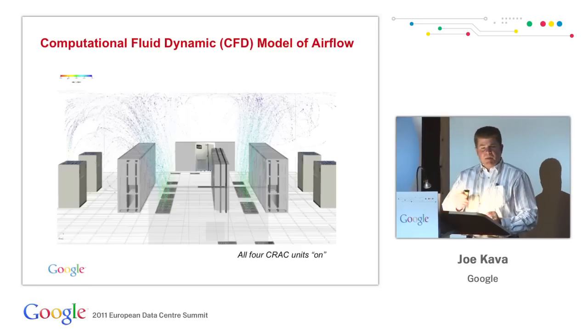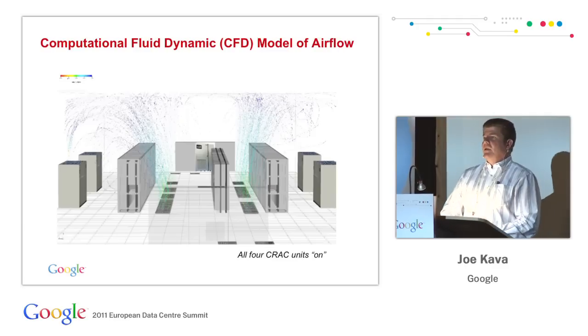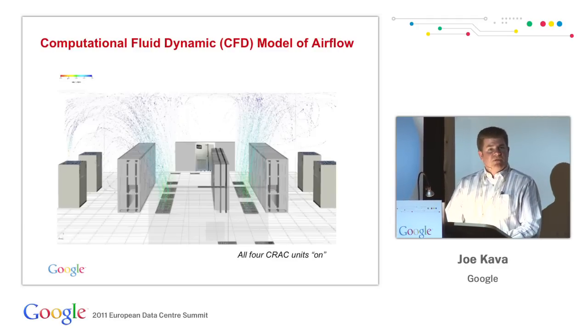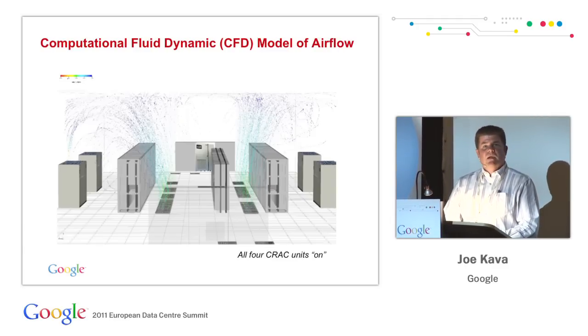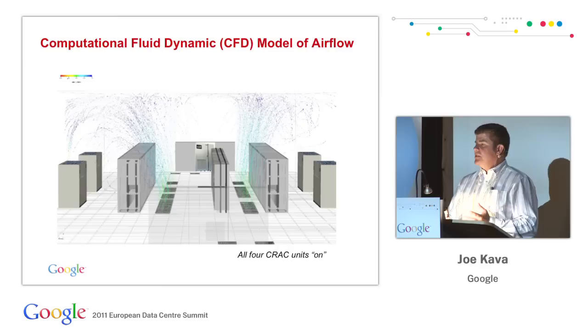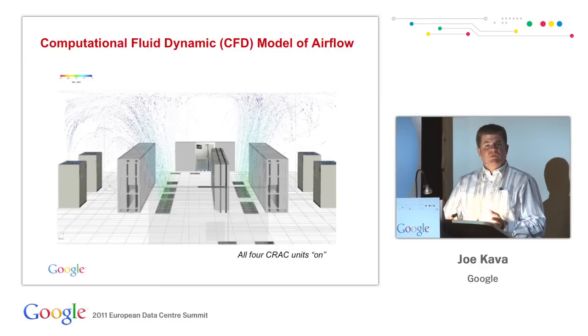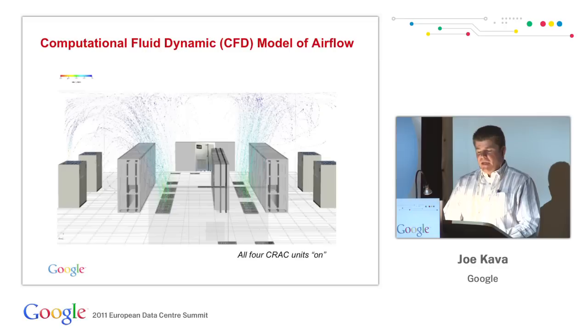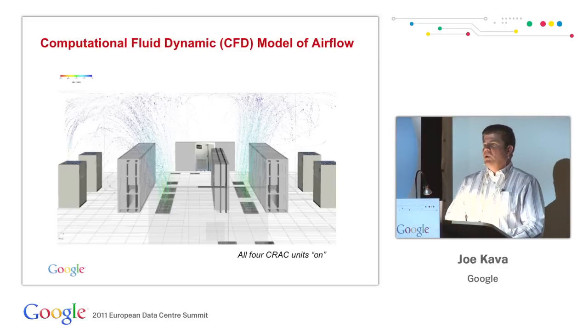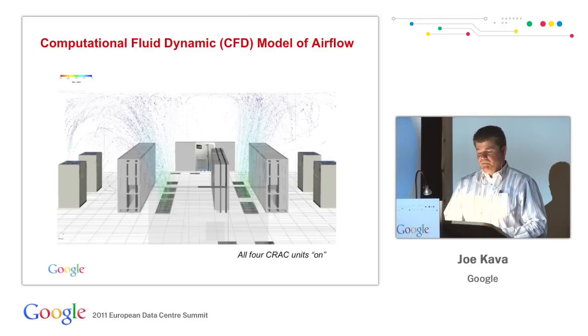So the first step was to do some modeling. We make extensive use of computational fluid dynamic modeling, and this helps us to visualize the airflow so that we can really see what's going on. And as we suspected, most of the airflow in the starting condition was blowing right by the IT cabinets and being completely wasted. It was terribly inefficient and just really a waste of energy.